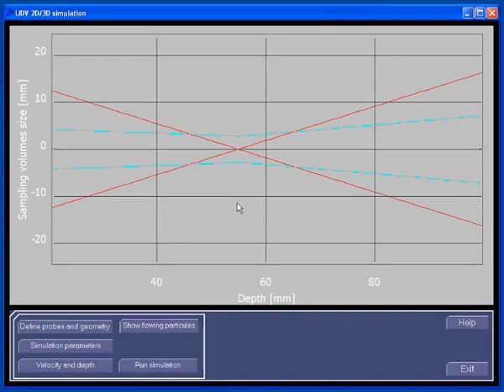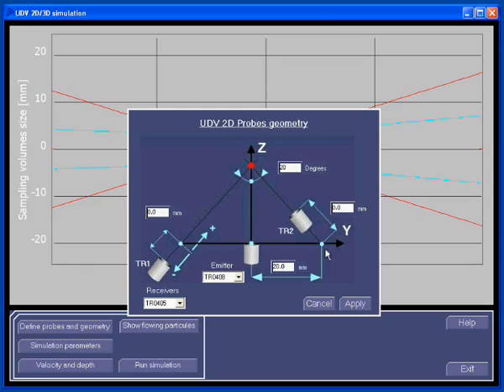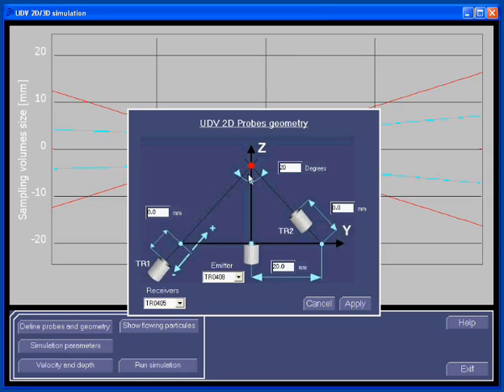Let's have a look at how the geometry of the probe is defined. For a 2D simulation, you see here the ultrasonic beam axis of the emitter and the ultrasonic beam axis of both receivers. Please note that all beam axes must cross at the same point. You can enter here the value of the angle between the ultrasonic beam axis of the emitting probe and the ultrasonic beam axis of the receivers — this angle must be the same for all receivers. You will enter in this button the distance between the emitting probe and the receiving probe; this distance must also be the same for all receivers. What can be fixed independently is the position of the receiving probe along its ultrasonic beam axis: for transducer 1, you put the value here, and for transducer 2, you enter the value here.